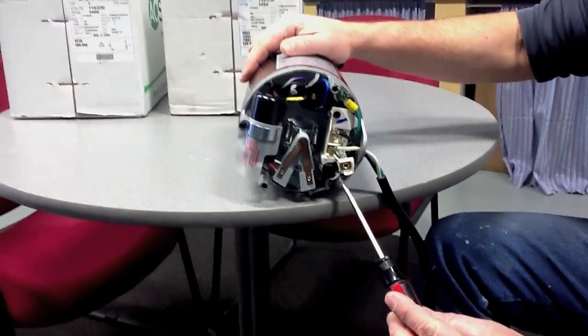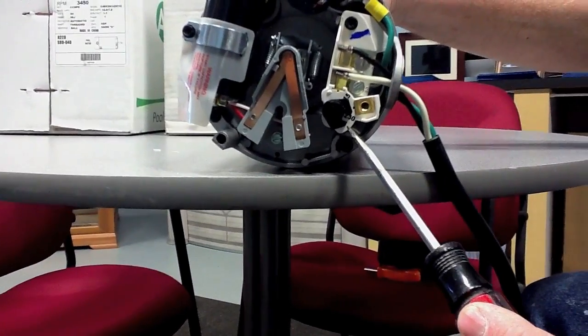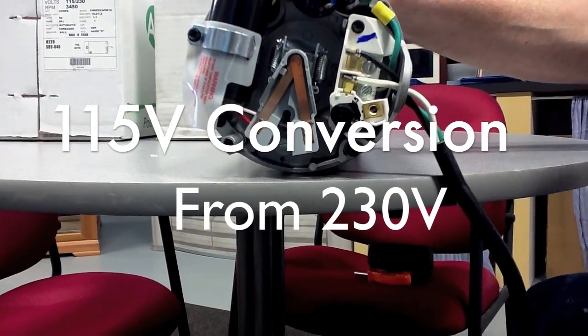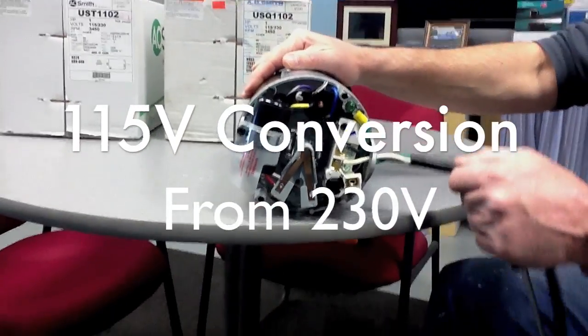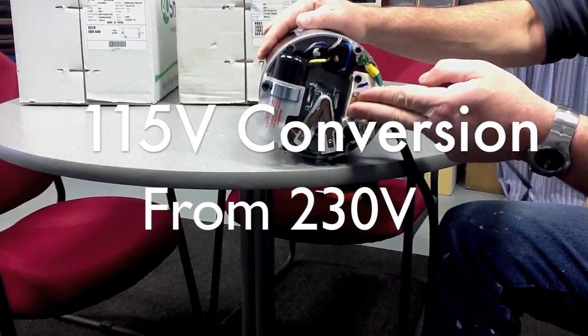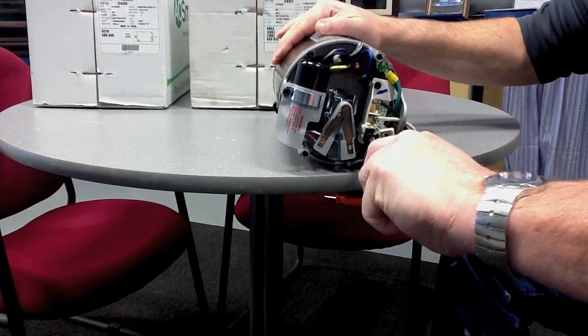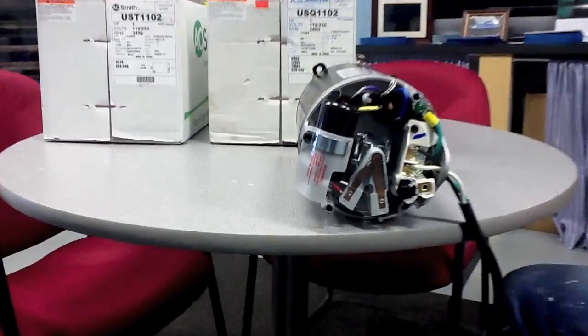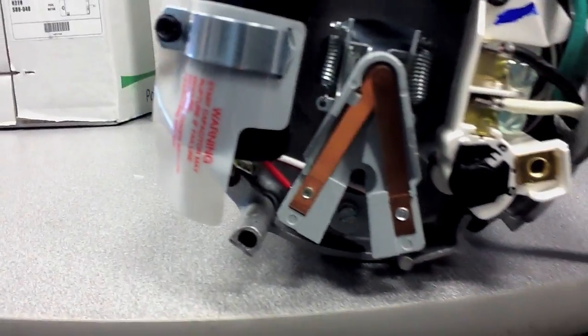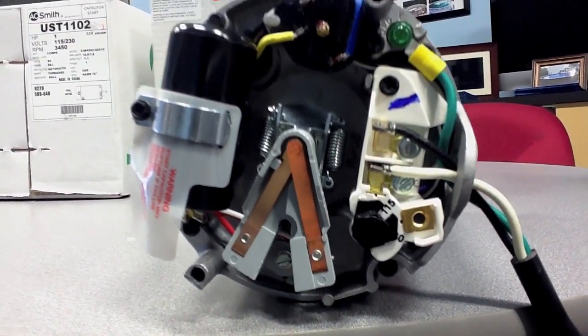On the newer models, it allows for easy adjustment. You can clearly see this motor is 230. If you were to have 110, you would wire the motor the same as we did — green to ground, black or white makes no difference — but your adjustment screw would allow you to flip it and move this motor to 115. This motor will now accept 115 volts as current.